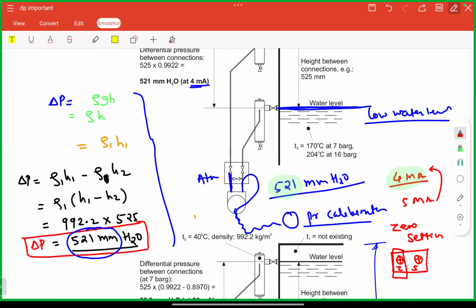The DP transmitter's diaphragm pressure calibrator that you set showed 5, 2, 1. If instead of 4 it is showing 5, it means there is a problem with the strain gauge, right sir? No, it is not a problem with the strain gauge. It is corresponding to that much strain. It was generating a 5 milliamp signal.